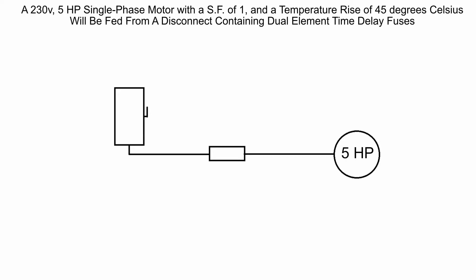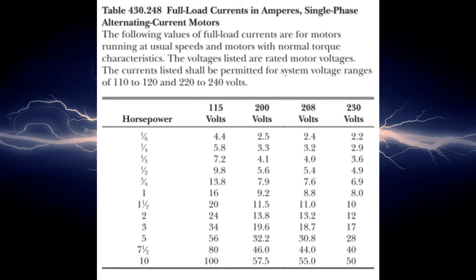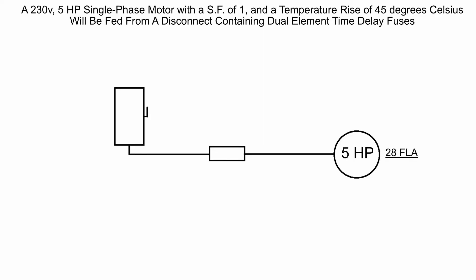The first thing we need to do is find the full load amps of this motor because we can't do a whole lot with just five horsepower. To do that we are going to go over to Table 430.248. This is the full load currents in amperes of single phase alternating current motors. We'll see that a five horsepower at 230 volts is going to be 28 full load amps.